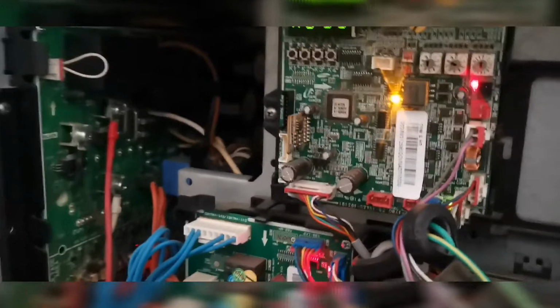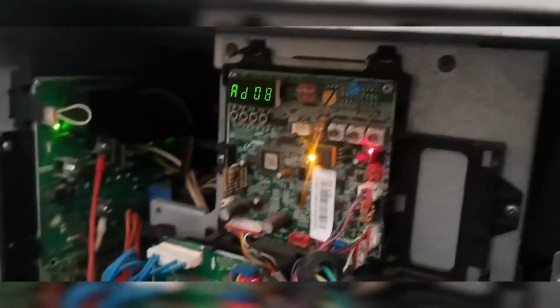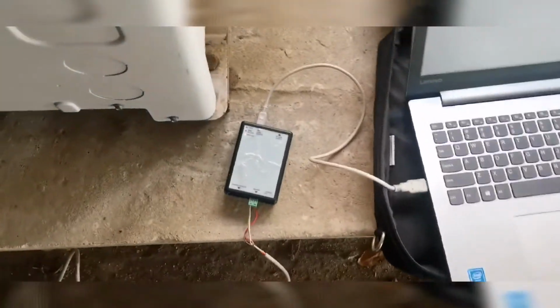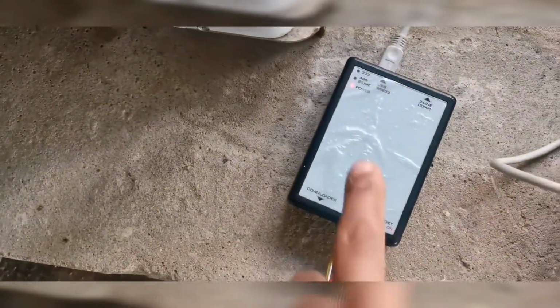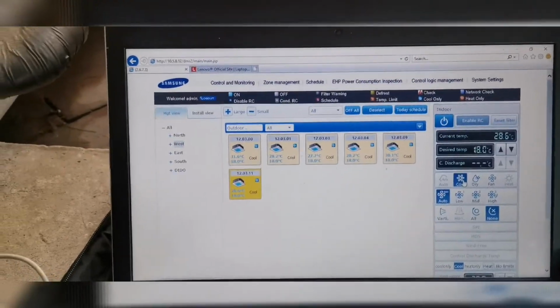So now we'll wait, and we'll start up the rest of the system in cooling mode and check that 2 units to verify whether or not we need to change the evaporator in and out sensors. So I'll give you guys some footage on my service checker. So there's my service checker. So this is the online setup.